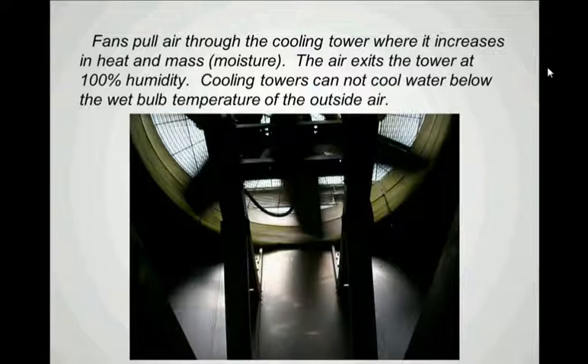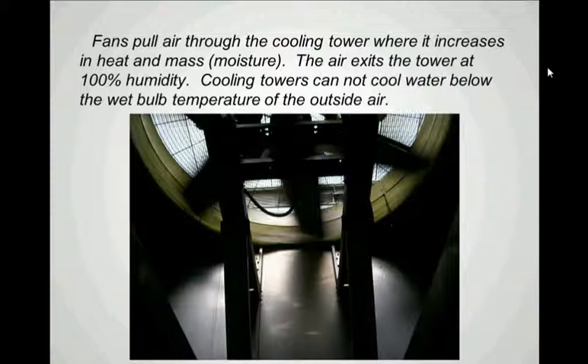The limiting factor is that cooling towers cannot cool water below the wet bulb temperature of the outside air. So there are some limitations, but in essence, by removing this waste heat in the cooling tower, we are able to fulfill the purpose of the cooling tower — that's to recycle the water and conserve water by sending it back to the point of heat exchange.